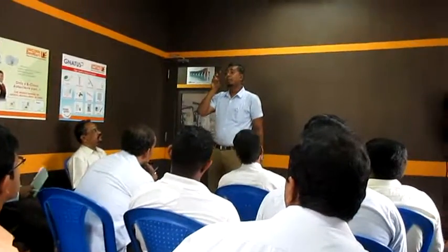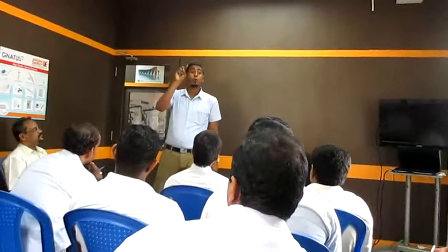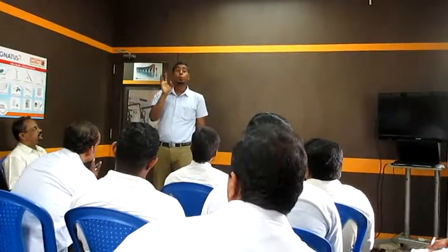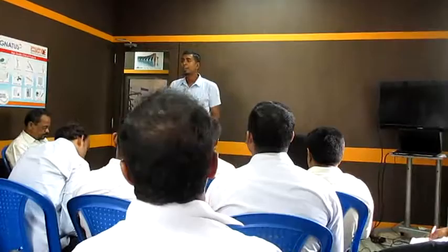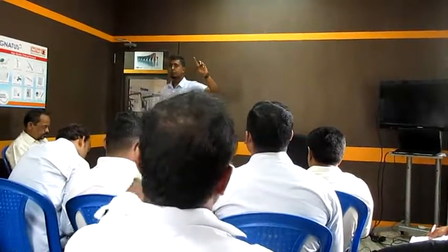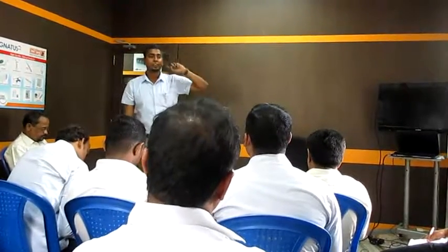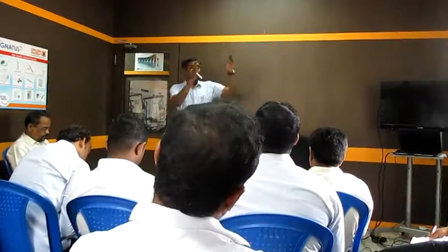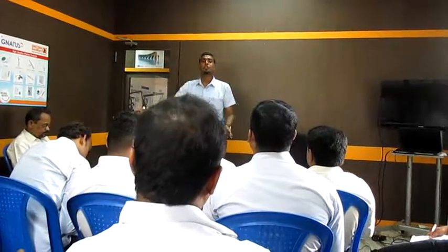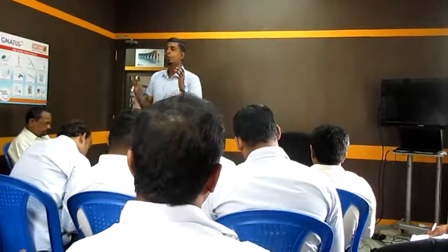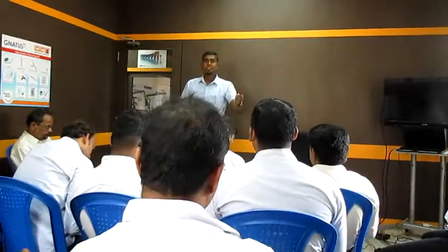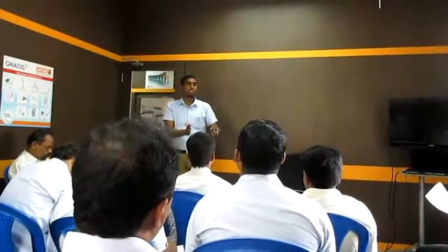That is why AERB said that QA of all the machines should be done. QA is a quality assurance test. A quality assurance test is nothing but a verification of these parameters, a verification of AERB guidelines against the specifications of the machine, to check whether the machine specifications are within the AERB guidelines or not.